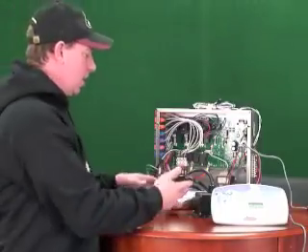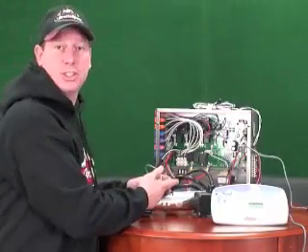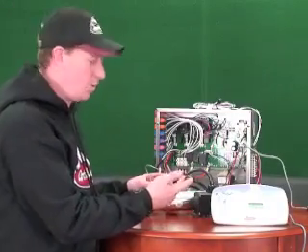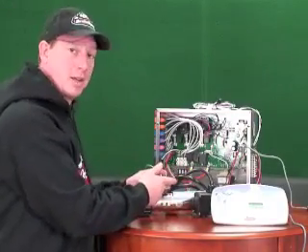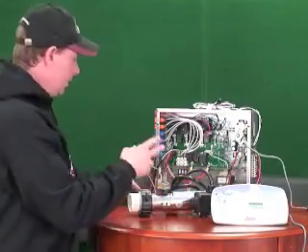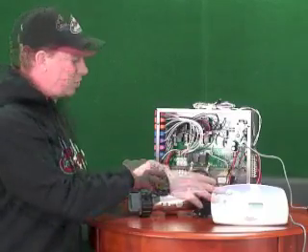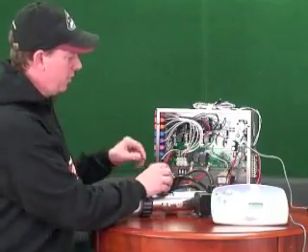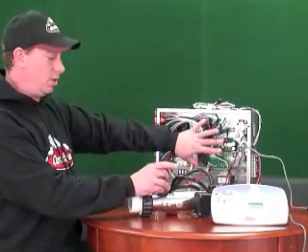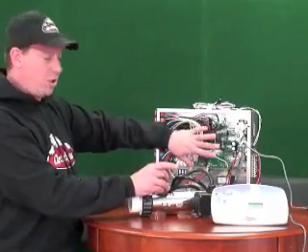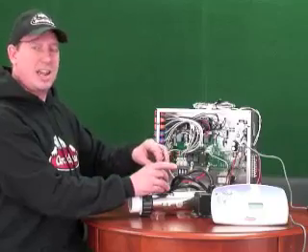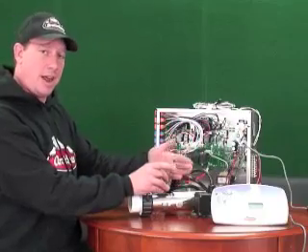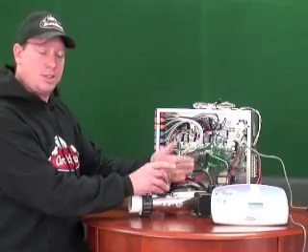So at this particular time I would know that everything is running and this pressure switch is faulty because it keeps going to flow. I can jumper and make it work and the flow goes away. You know that there is no malfunction within the board and the operation or this cable. Everything is running perfectly fine up till this switch.